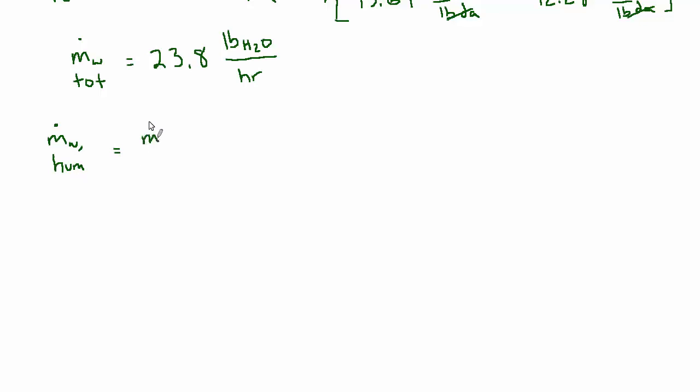the mass flow rate total minus the mass flow rate of the occupants. So that's 23.8 pounds per hour minus 6.67 pounds per hour, which equals 17.1 pounds per hour. And that's the answer to part A.